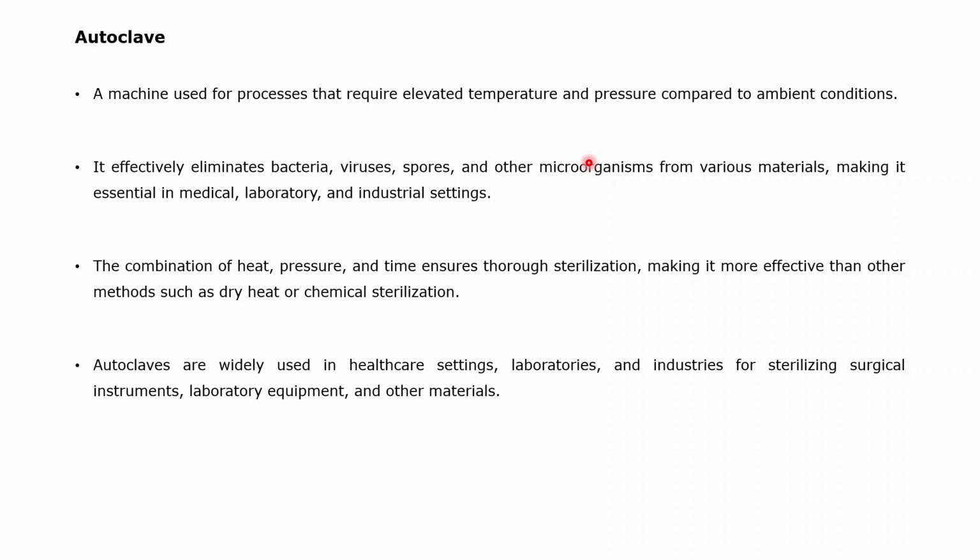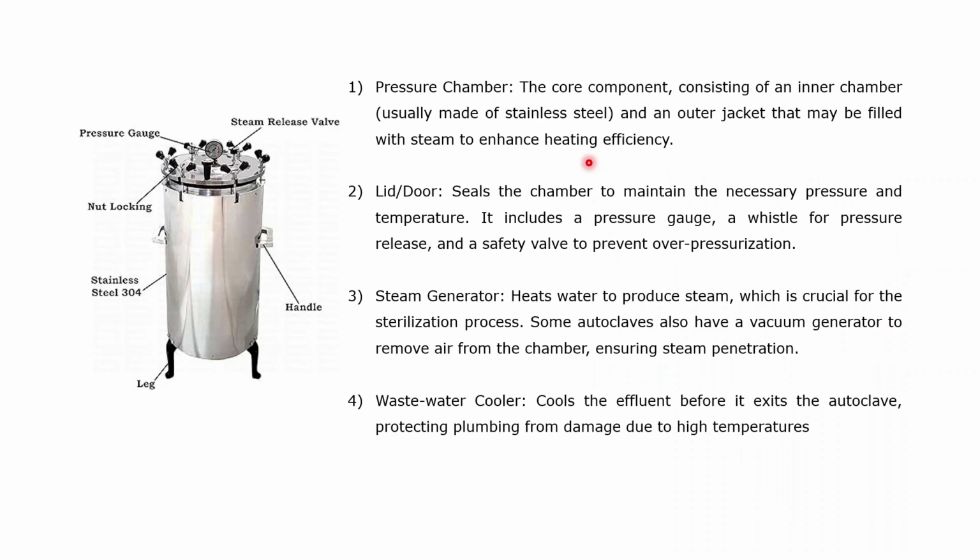If you move on to the components present within an autoclave, you can see this image of the autoclave here. There are several components. The first one is the pressure chamber. Mainly it is made of stainless steel to withstand the high temperature and pressure that is happening within the autoclave once it is on.